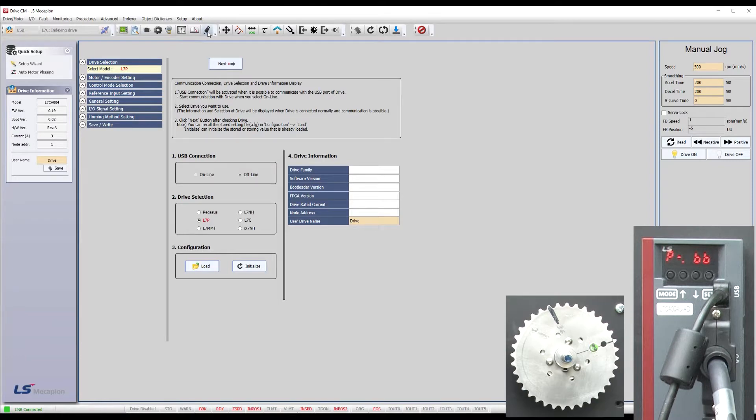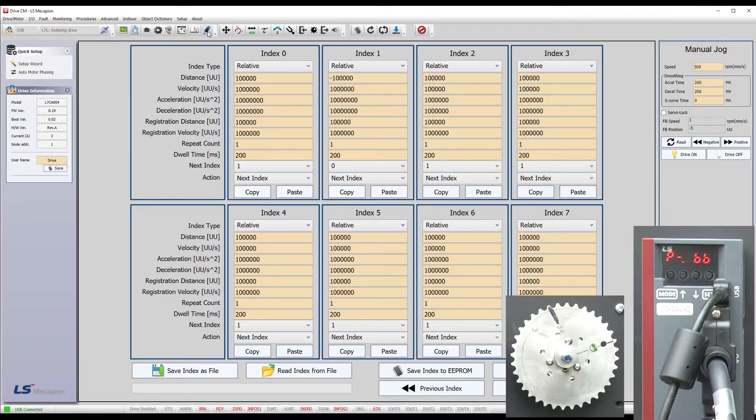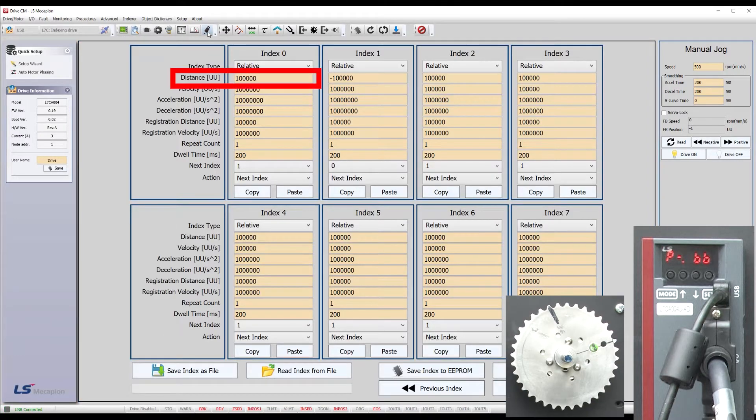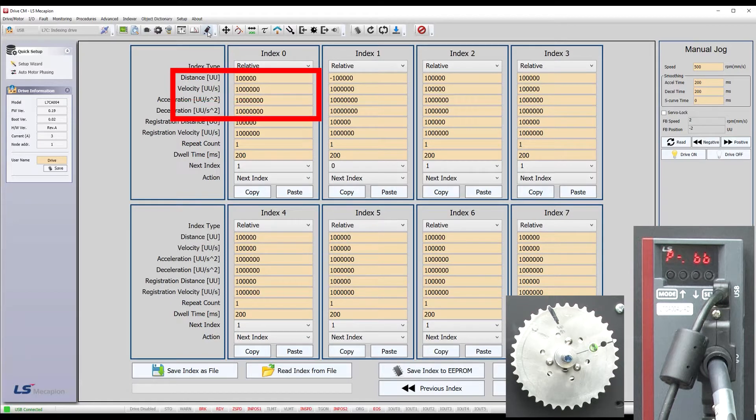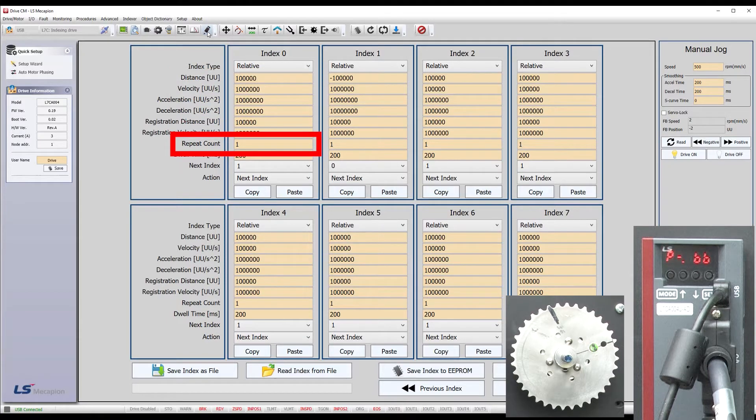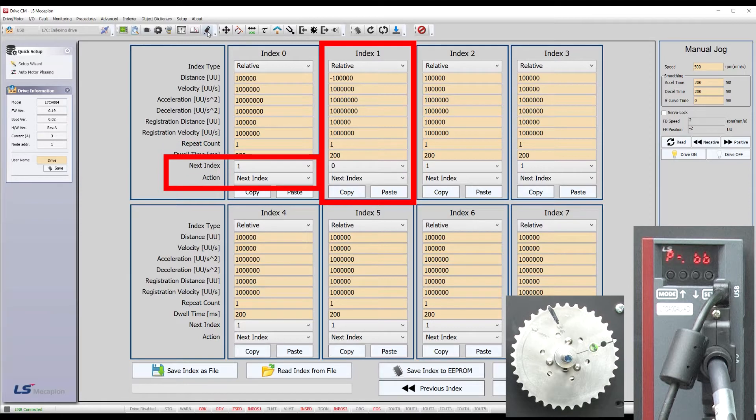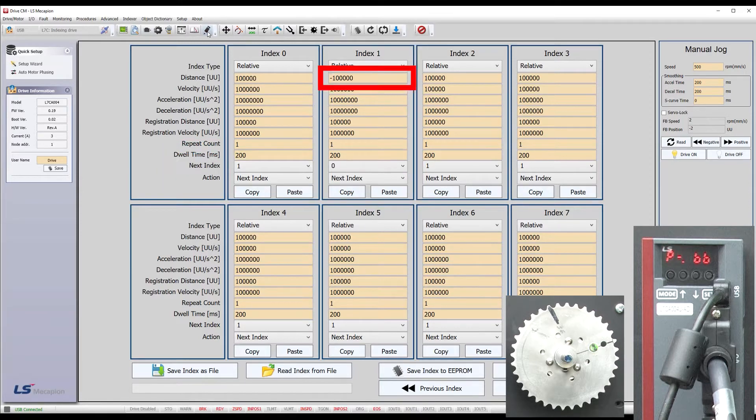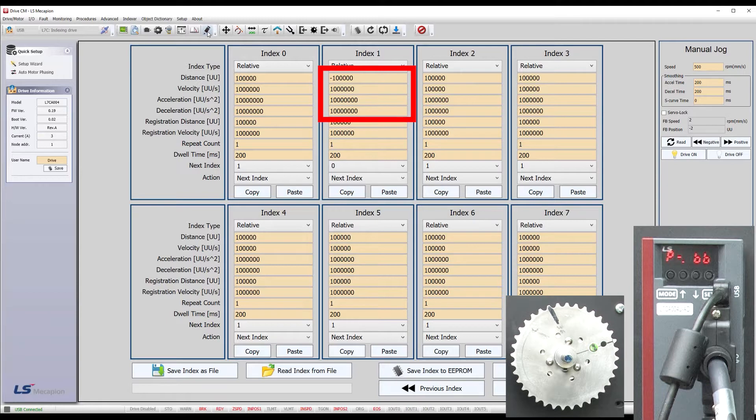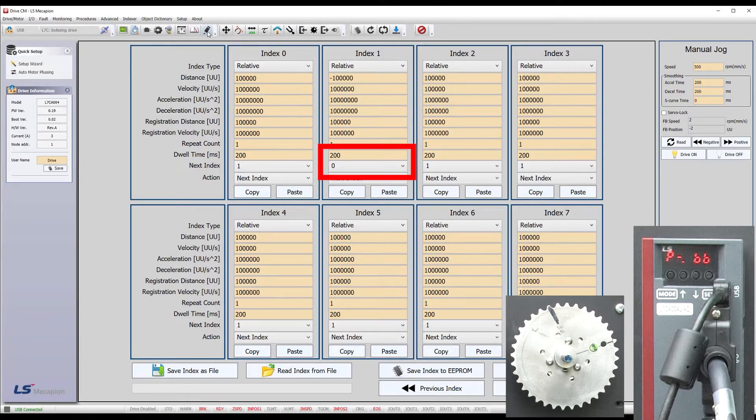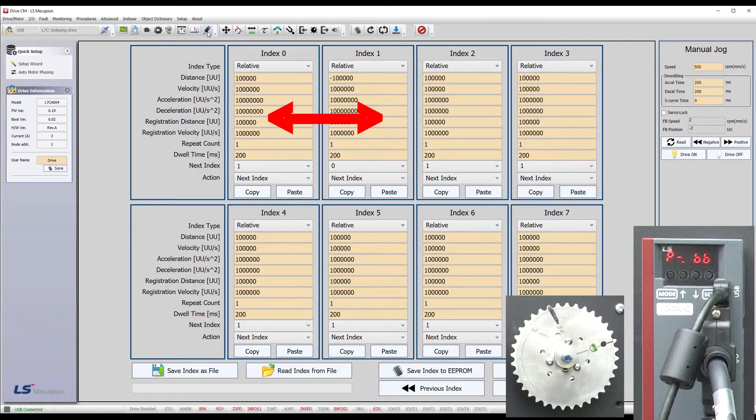I've already set up an indexing motion profile. It just says rotate 100,000 user units at this rate using these accelerations. Do it once, wait 200 milliseconds and then go to index 1. Index 1 says go back 100,000 user units using the same velocity accelerations. Wait 200 milliseconds and then go back to index 0. So, this back and forth motion will just repeat over and over.